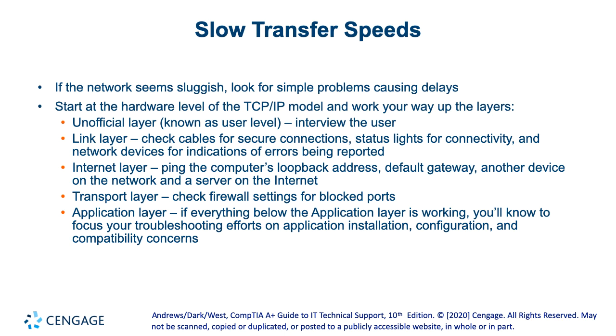Next, look for any loose cables or cables that might have too much shielding stripped away. There should be less than 1 inch of cable stripped away at each end—any more than that and you can have issues with the cable interfering with itself.